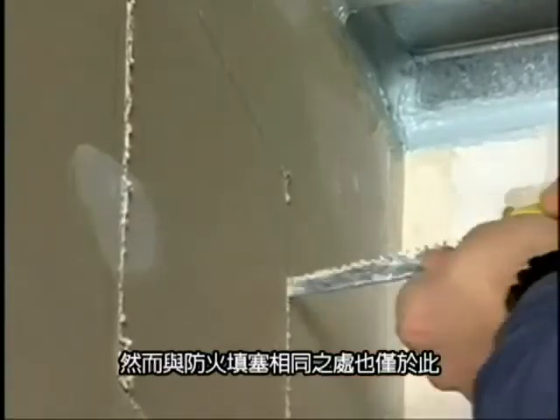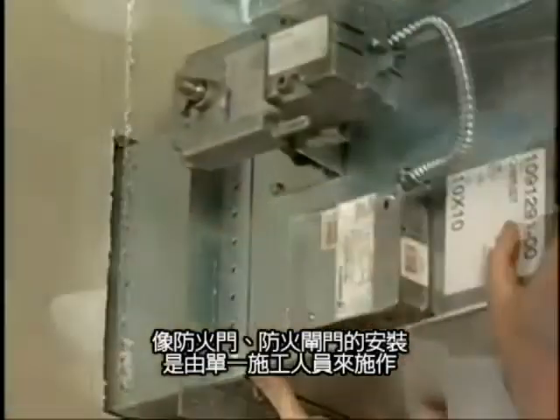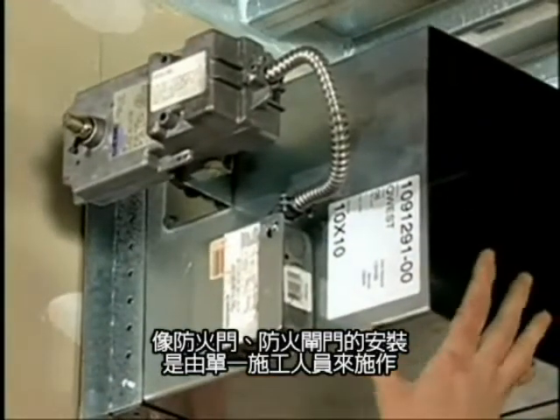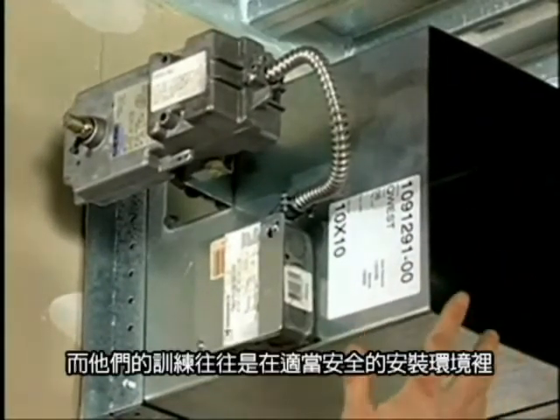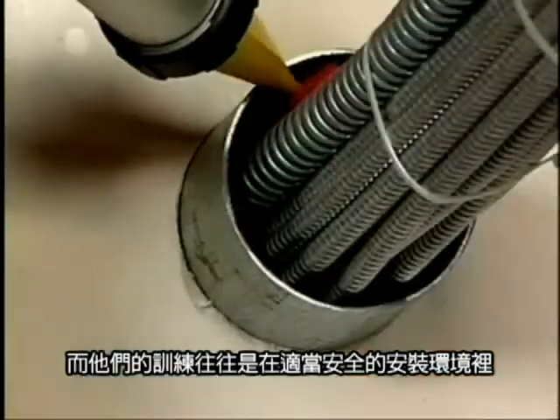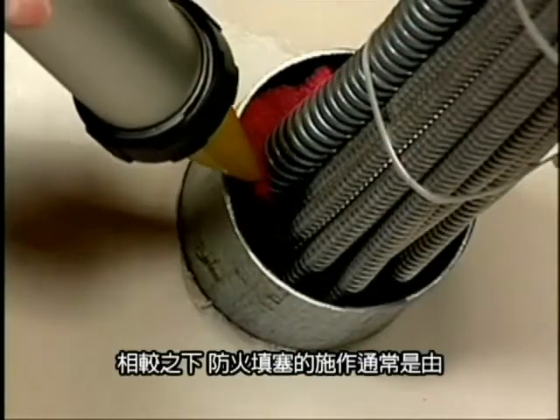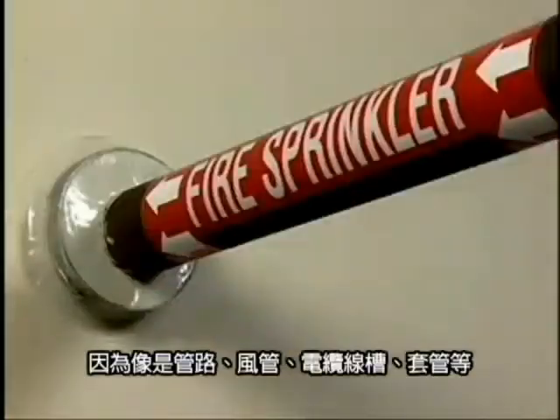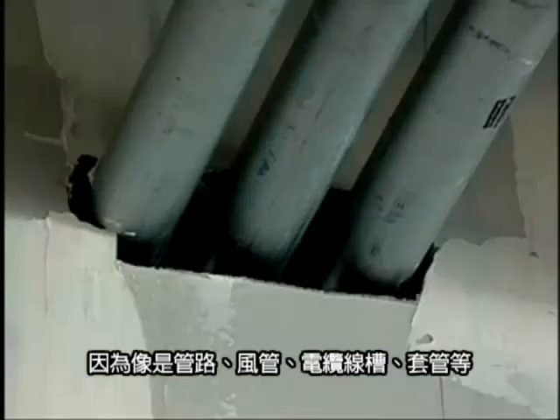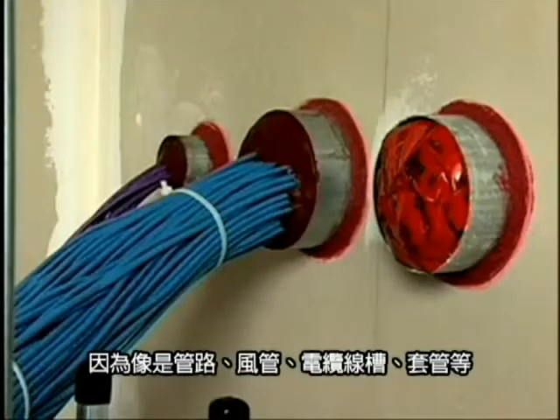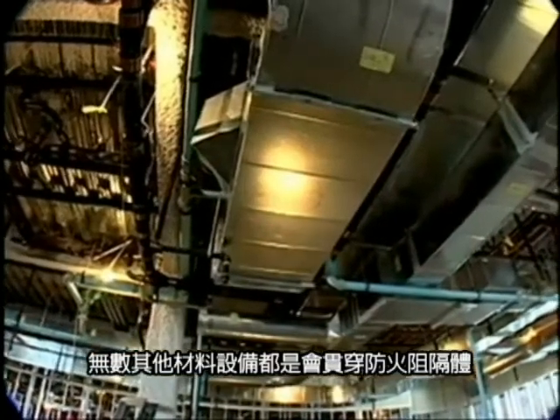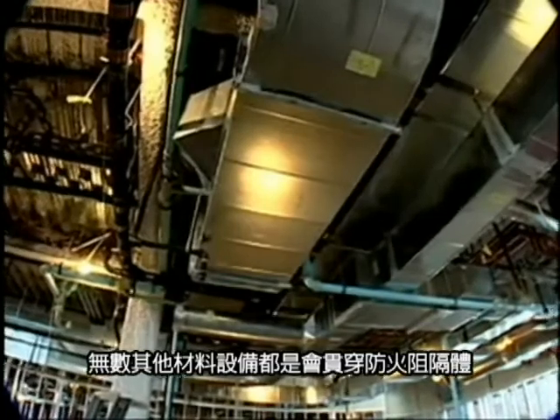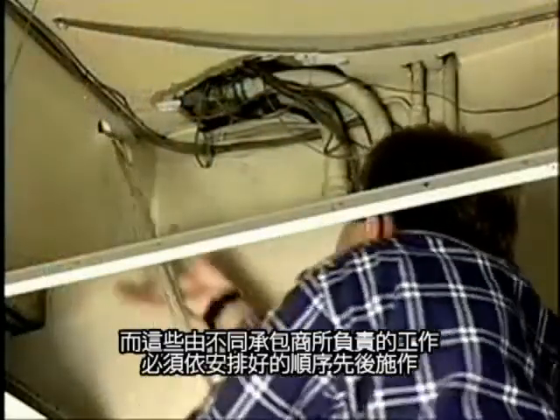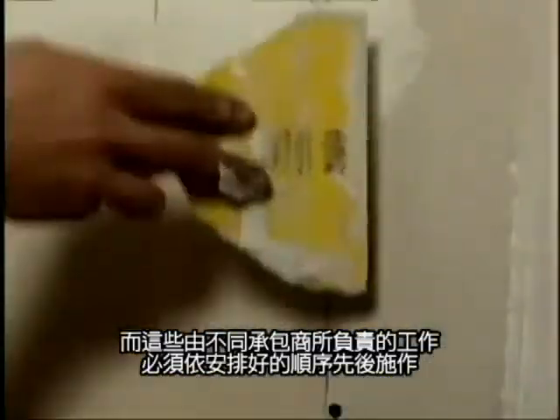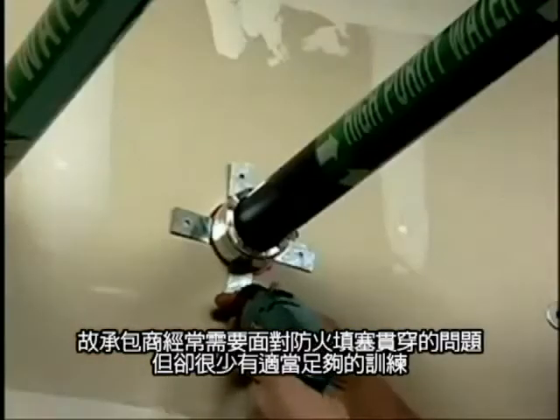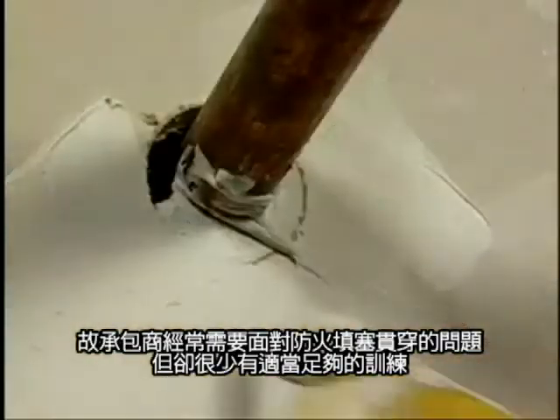The similarities, however, end there. Doors and dampers, for example, are all installed by a single craft, each of whom are trained in their proper and safe installation. Fire Stop, by contrast, is installed by nearly every craft because pipe, duct, conduit, cable tray, sleeves, and an infinite number of other service items all need to penetrate barriers. Because the work done by various sub-trades usually follows other crafts, these trades are often faced with fire-stopping penetrations as well, and rarely with adequate training.